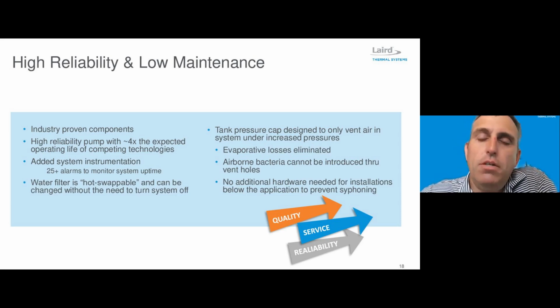Again, with the automobile analogy, the radiator on the front of an automobile has a pressure cap, and it seals off the system from the external environment unless high pressures are achieved. And so that's what we have. Under normal operating pressures, this system is closed off from the environment all the time. There's no biogrowth, there's no evaporative losses, and this really provides a distinct advantage for our users. When you think of the maintenance required on an automobile cooling system, it might be 100,000 miles, which depending upon how many miles you drive, could be upwards of 8 years. So we really anticipate that this is a very low maintenance design that can provide some true benefits to our customers.